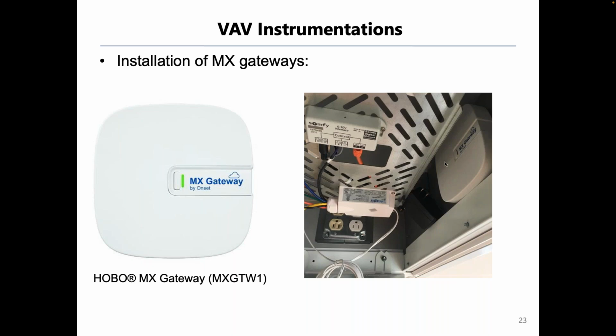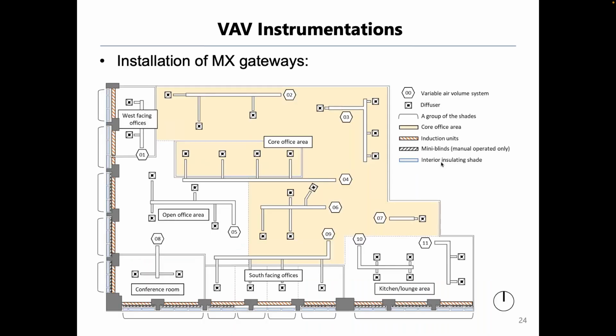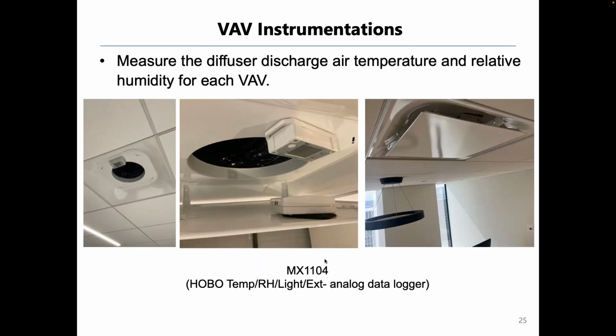So we installed these gateways throughout the space. And if you see it, we initially had 2 gateways to monitor the entire space. We realized sometimes the signal is weak, especially for these loggers towards the north side here. So we added the 3rd one here. But I would say even with 2, with some optimization, could have covered this space. And they collected data very well. So we are so happy and fortunate we were able to use this feature.